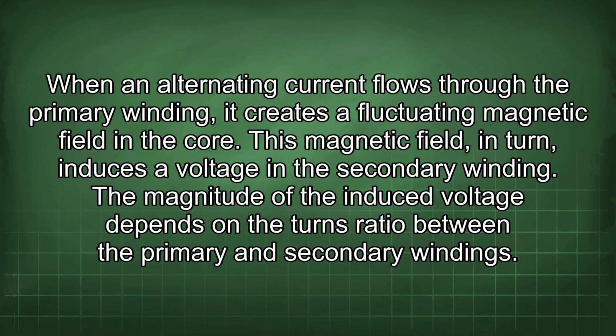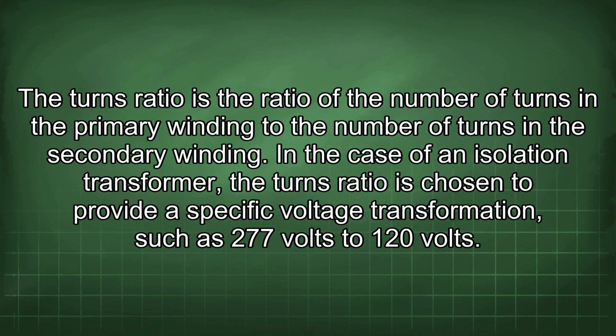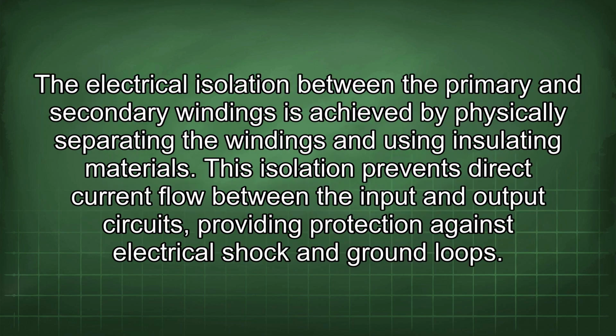The magnitude of the induced voltage depends on the turns ratio between the primary and secondary windings. The turns ratio is the ratio of the number of turns in the primary winding to the number of turns in a secondary winding. In the case of an isolation transformer, the turns ratio is chosen to provide a specific voltage transformation, such as 277 volts to 120 volts. The electrical isolation between the primary and secondary windings is achieved by physically separating the windings and using insulating materials. This isolation prevents direct current flow between the input and output circuits, providing protection against electrical shock and ground loops.